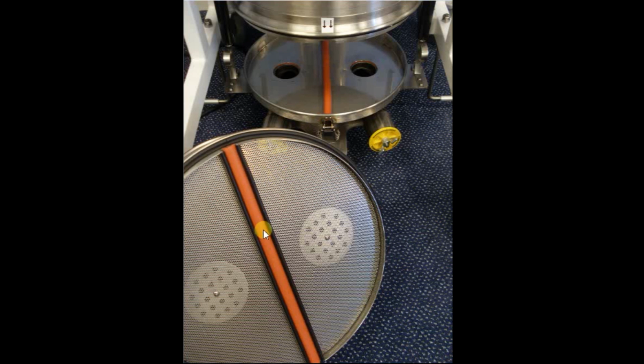If this seal or this seal become damaged or worn, then you may start to see a high inspired CO2 value on your capnograph, because exhaled gas is bypassing the soda lime and going straight to the inspiratory side. That's quite rare. These seals are very good. They don't soften too much with use, and they normally prevent that happening. But just look out for breakdowns or crumbling of the orange seal here and at the other end particularly, as they may be the first places to go, and then you may start to see an inspired CO2 problem.